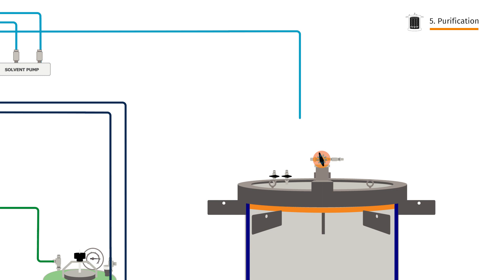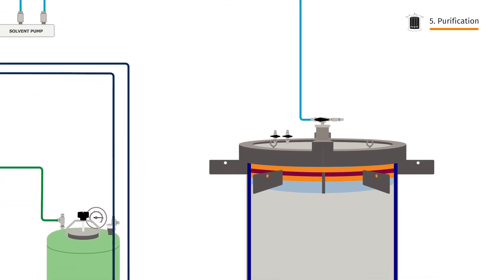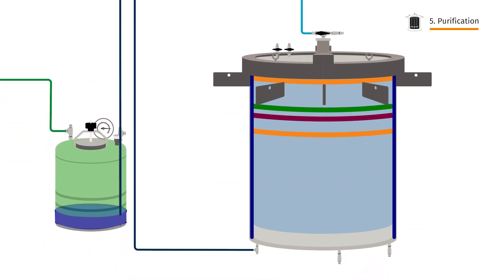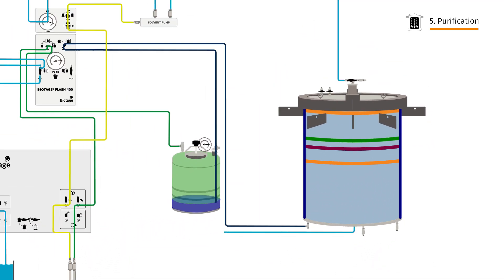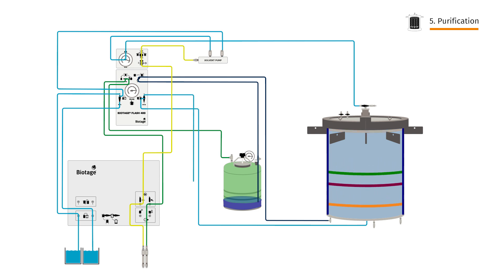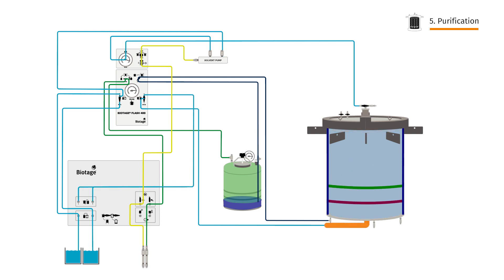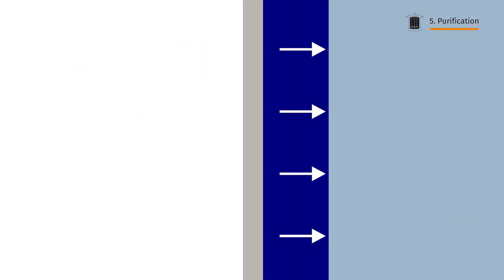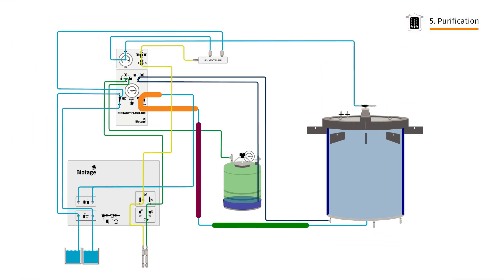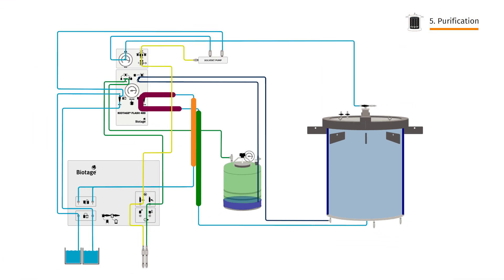The mobile phase will carry sample through the Flash 400 cartridge. The sample components travel at different rates, resulting in predictable purification. Meanwhile, the radial compression module is pushing back on the cartridge from all sides, ensuring that the media bed in the cartridge is intact and fully functional.